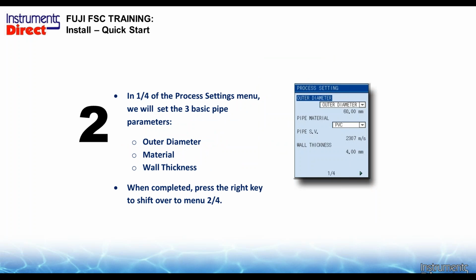Now on 1/4 of the Process Setting menu, there's three basic parameters: the pipe outside diameter, the material, and the wall thickness. The OD is obtainable from our ANSI pipe chart book. You can download it from the website. It comes with the flow meter there, or if you had a thickness gauge itself.